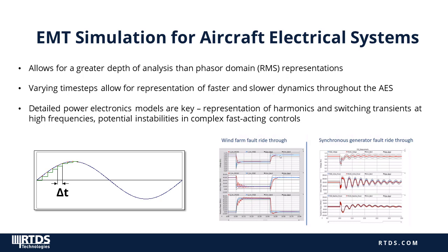EMT simulation is a much deeper dive than traditional models for power systems planning — i.e., phasor domain or RMS representations, positive sequence only analysis. This additional detail is so important for power electronics-dominated aircraft electrical systems. It allows for analysis of harmonics and switching transients at frequencies of tens or even more than 100 kHz, and it allows for representation of low-level converter controls. We get insight into the system's behavior through a huge variety of failure modes and can capture behavior that would be invisible in a phasor domain approach.